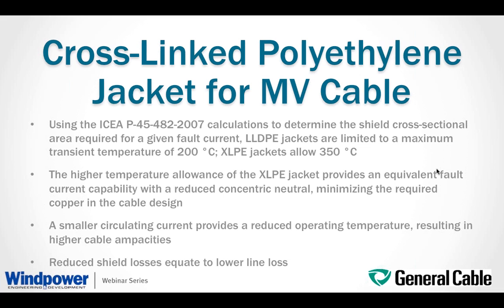The way this is calculated is that you start with the normal rated operating temperature of your cable, so it's 90 or 105 C, depending on how you design your system. Based on that temperature, you have a given neutral temperature, and then what you measure is the amount of copper that you need in the neutral to sustain the temperature rise for a certain fault duration without damaging the cable core or the jacket, maintaining the integrity of the cable.